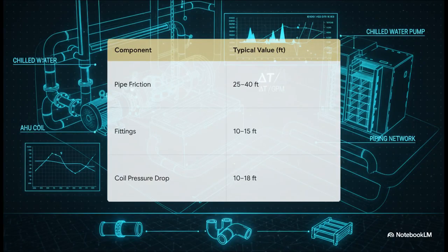And just to give you a feel for what we're talking about, in a pretty standard system, just the pipe friction alone can add up to 25 to 40 feet of head. Then you toss in the resistance from all the fittings and the pressure drop across the cooling coils, you can see how fast that total pressure requirement, the total head, really starts to build up.